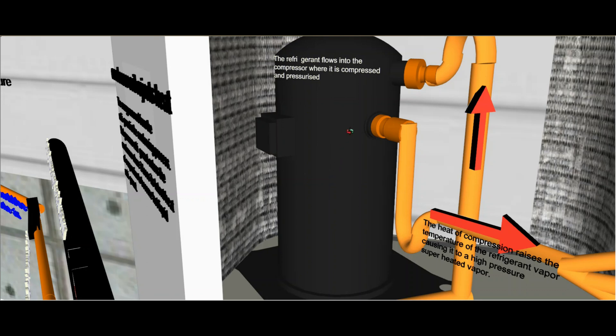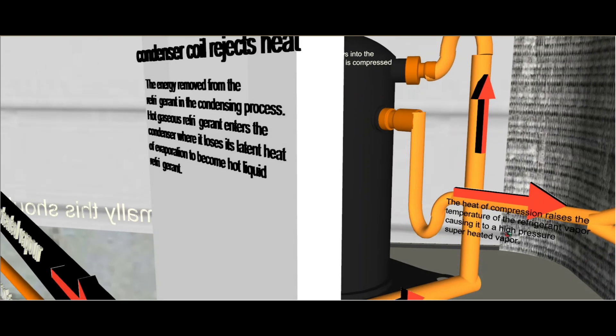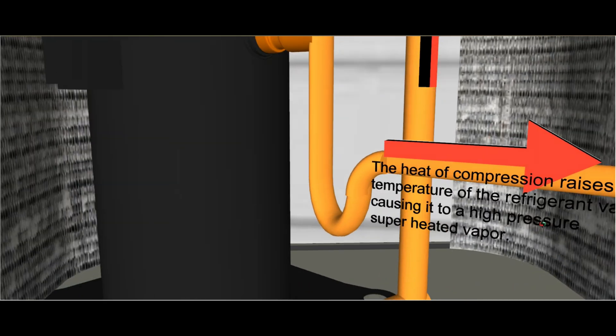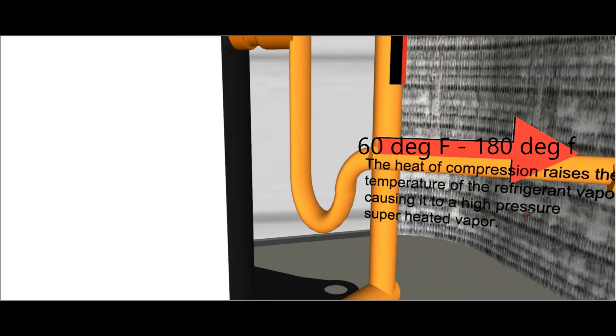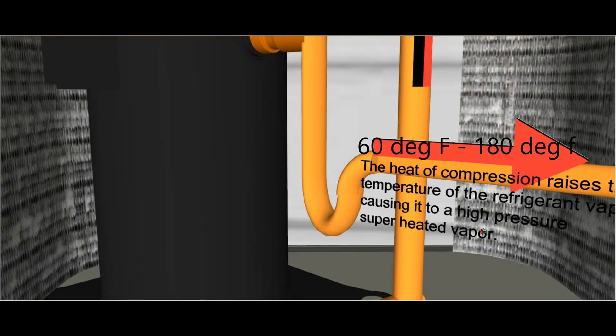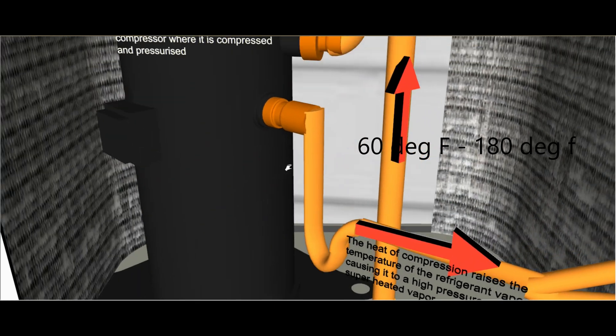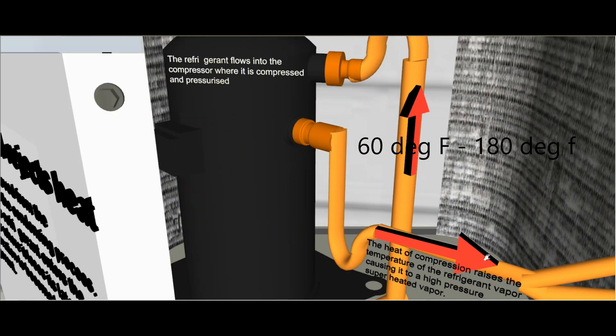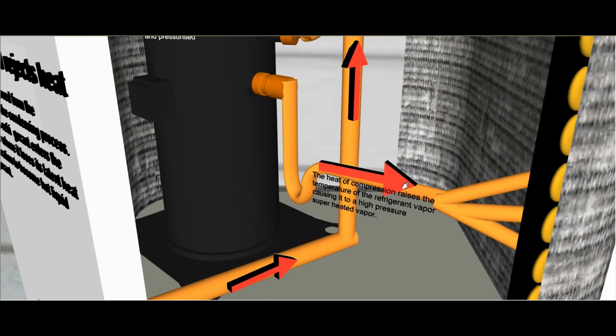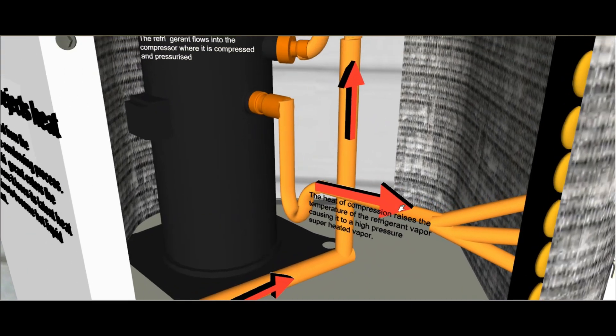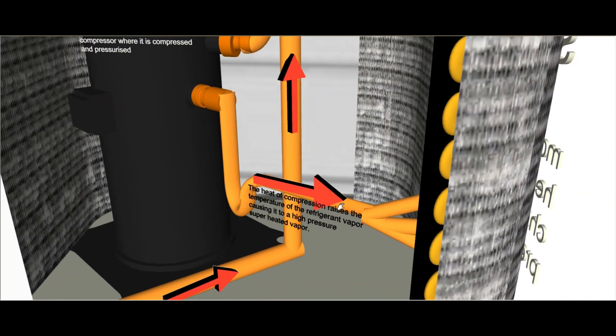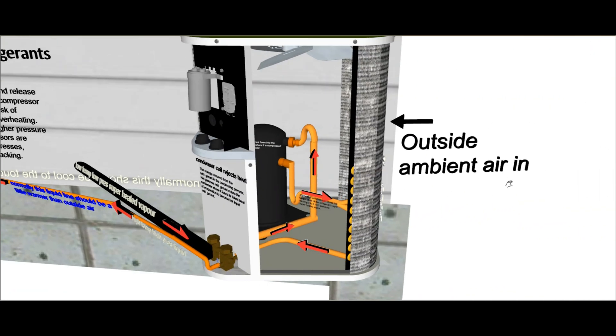So it's going to come out an even hotter temperature here. So the heat of compression raises the temperature of the refrigerant vapor, causing it to a high pressure superheated vapor. So it's going to get even hotter here, so it'll jump from 60 degrees Fahrenheit to about 180 degrees Fahrenheit, and that's hot. Now remember, hot is attracted to cold. If this is 180 degrees Fahrenheit and we have about 80 degrees Fahrenheit here, it's not going to be attracted to it because this is hotter than this outside temperature, so it's going to reject it.